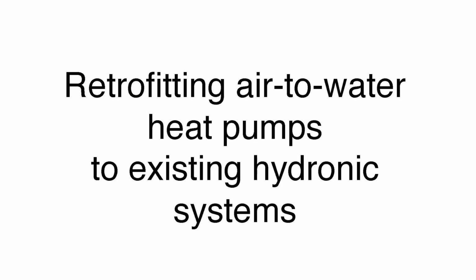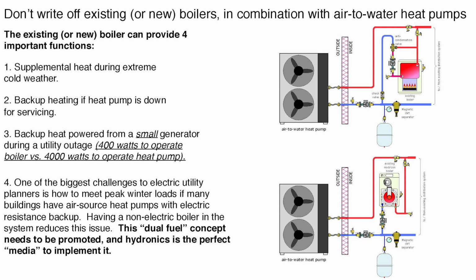Retrofitting, okay? Don't throw away the boiler is the takeaway here. I've talked to people that have very good ideals in mind, but they hate fossil fuel. They absolutely think fossil fuel is the scourge of the earth. And the first thing they want to do is rip out a boiler. If the boiler has service life left, leave it in the system. It could eventually go away. Maybe it's replaced by something else. Maybe it'll be replaced by an electric boiler. But it's backup, it's supplemental heat, and really importantly, you can run a boiler, residential boiler, on a very small little backup generator. Like a little Honda generator you could set on a table. That would run a hydronic system. As long as you keep gas in the generator, your house isn't going to freeze.